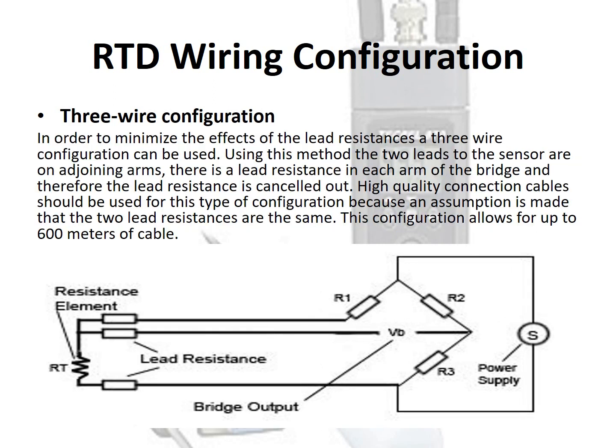In order to minimize the effects of lead resistances, a 3-wire configuration can be used. Using this method, the two leads to the sensor are on adjoining arms, with a lead resistance in each arm of the bridge, and therefore the lead resistance is cancelled out. High quality connection cable should be used because an assumption is made that the two lead resistances are the same. This configuration allows for up to 600 meters of cable.